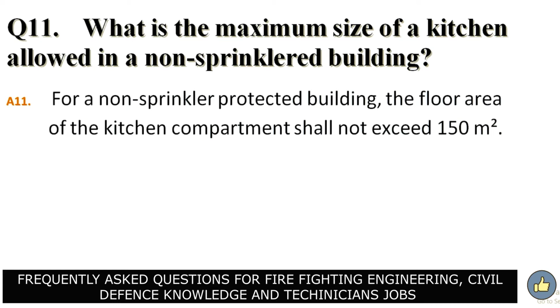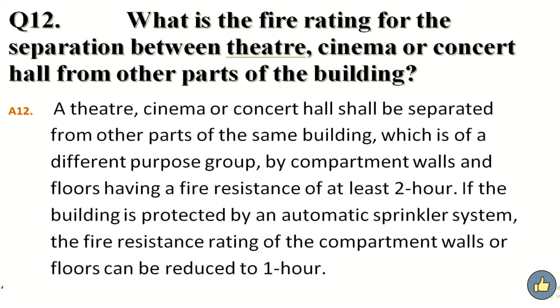Answer. For a non-sprinkler protected building, the floor area of the kitchen compartment shall not exceed 150 square meters. What is the fire rating for the separation between theatre, cinema or concert hall from other parts of the building? Answer. A theatre, cinema or concert hall shall be separated from other parts of the same building which is of different purpose group by compartment walls and floors having a fire resistance of at least 2 hours.